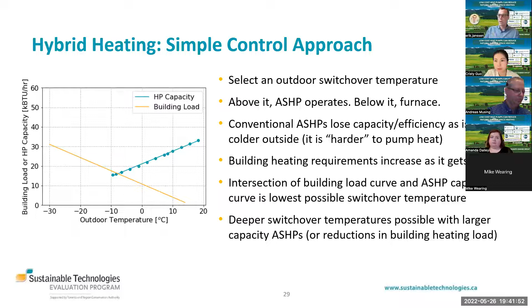An important thing to note about air source heat pumps is that they're going to typically lose capacity and efficiency as it gets colder outside, because it gets harder to pump heat. Again, using our water pump analogy, if we're trying to pump water up a taller hill with the same pump, typically we'll get a lower flow. Well, in the case of air source heat pumps, the hill is the temperature difference between the outside and inside, and that's called the lift. And the greater that temperature difference, the lower the heat transfer is going to be.